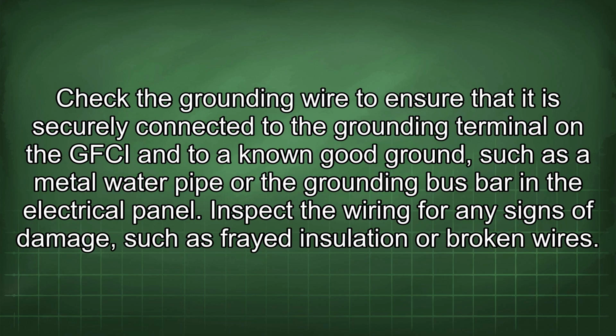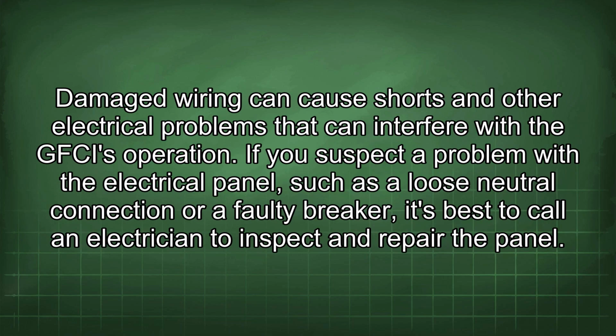Check the grounding wire to ensure that it is securely connected to the grounding terminal on the GFCI and to a known good ground, such as a metal water pipe or the grounding bus bar in the electrical panel. Inspect the wiring for any signs of damage, such as frayed insulation or broken wires. Damaged wiring can cause shorts and other electrical problems that can interfere with the GFCI's operation.